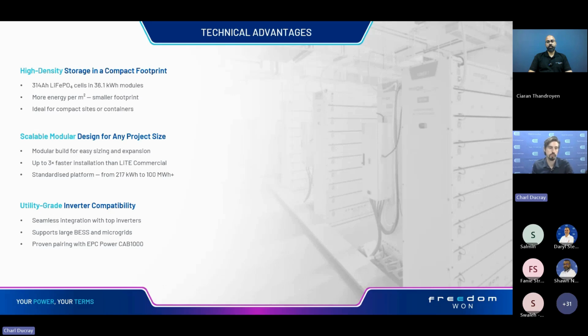Specifically speaking of the megaTower Extra, which has that higher voltage, the megaTower is compatible with utility grade inverters. So as many of you will know, if you've worked with the commercial inverter options that are available in the market as things stand, you generally reach your limit when you're looking to parallel about 4 or so inverters. Generally speaking, you're capped at about 2 megawatts on the inverter side. So the importance of bringing in the compatibility with utility grade inverters was that we wanted to move away from that limitation, whereby we could parallel not only as many batteries as we want, but as many inverters as we want as well.